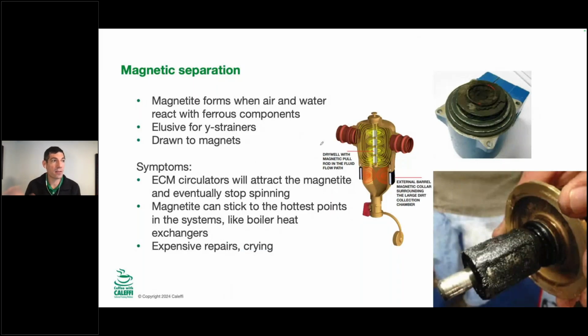Another advantage, matched with the technology in the industry, is magnetic separation. A magnetic separator is going to catch the magnetite, and it's going to cling to the magnet. The devices that we make are all in a dry well. So you turn off the system, you pull out the magnet, you pull this one off of the outside, the magnetic debris that looks like an Etch-a-Sketch falls down to the bottom, and you purge that out.